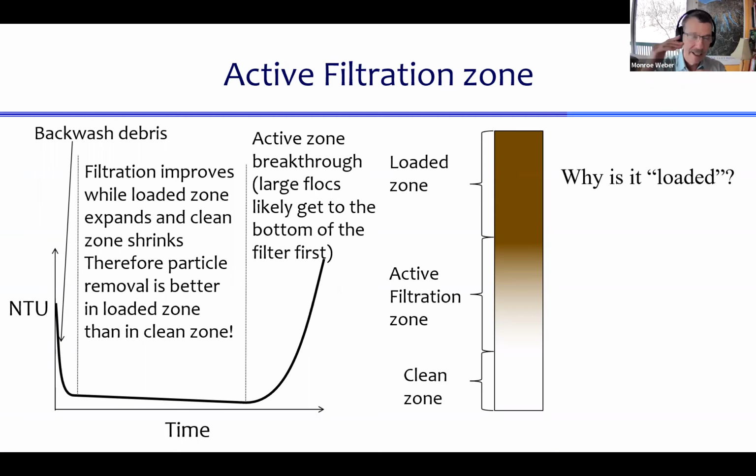And in the middle, there's this active filtration zone where it's actually very effective, where most of the particles are being captured. And then the filter goes through what we call breakthrough. Breakthrough is when the turbidity or some of the particles start showing up in the effluent, coming out the bottom of the filter.